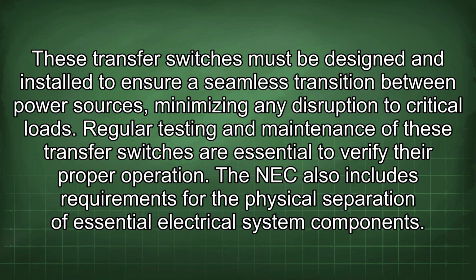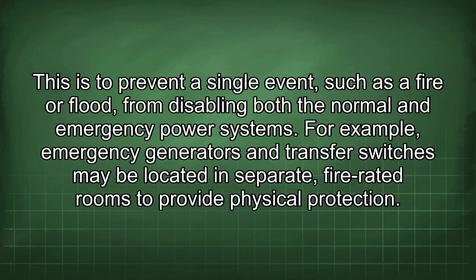The NEC also includes requirements for the physical separation of essential electrical system components. This prevents a single event, such as a fire or flood, from disabling both the normal and emergency power systems. For example, emergency generators and transfer switches may be located in separate, fire-rated rooms to provide physical protection.